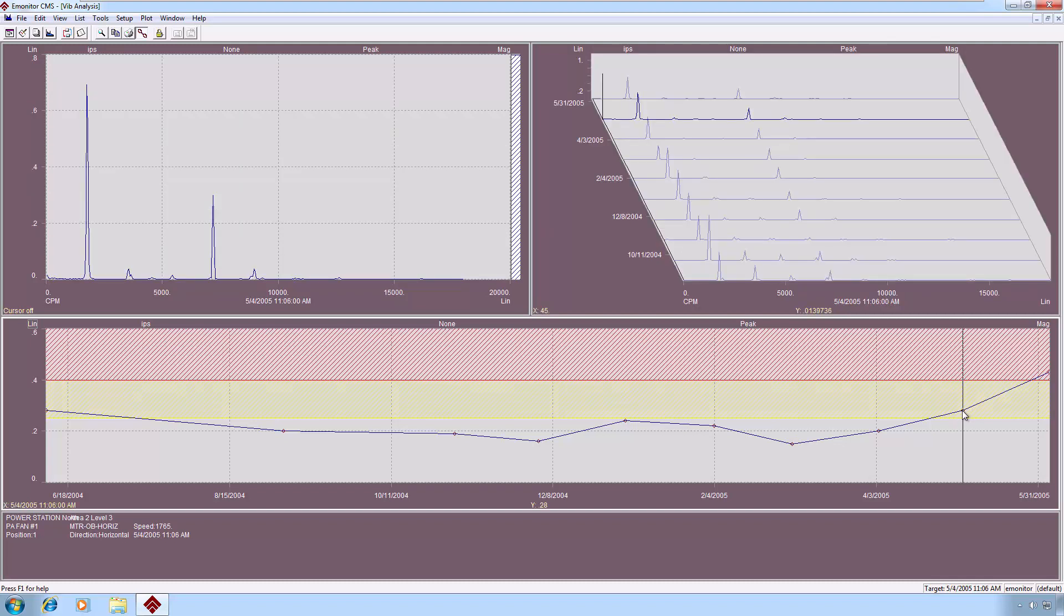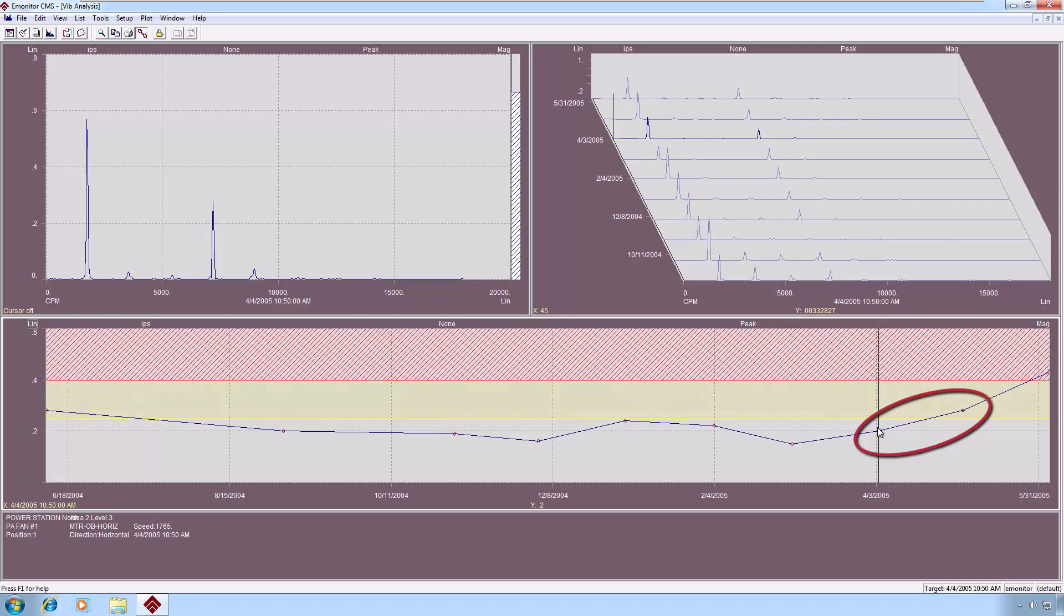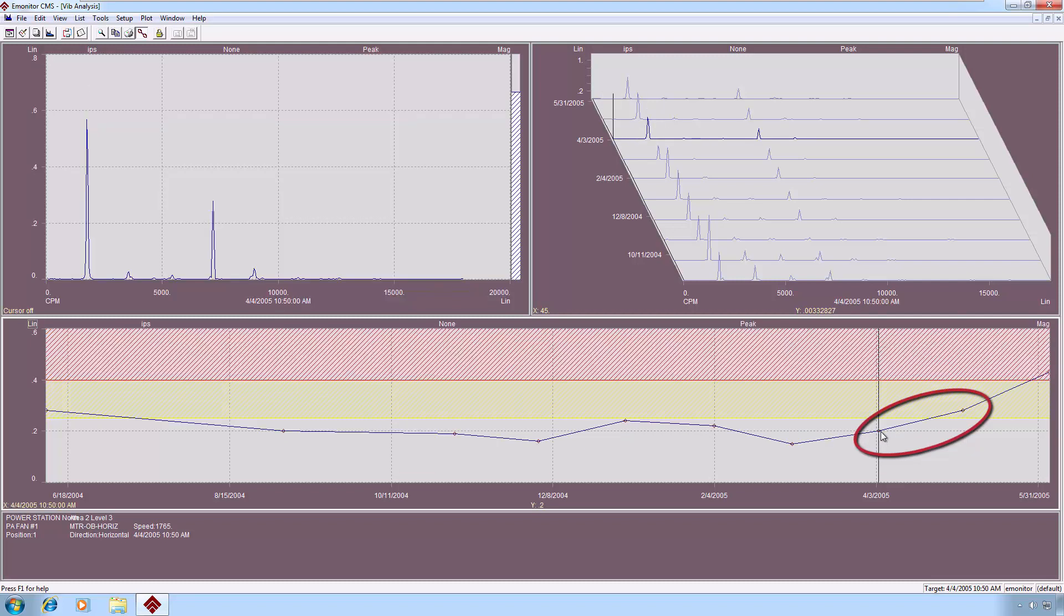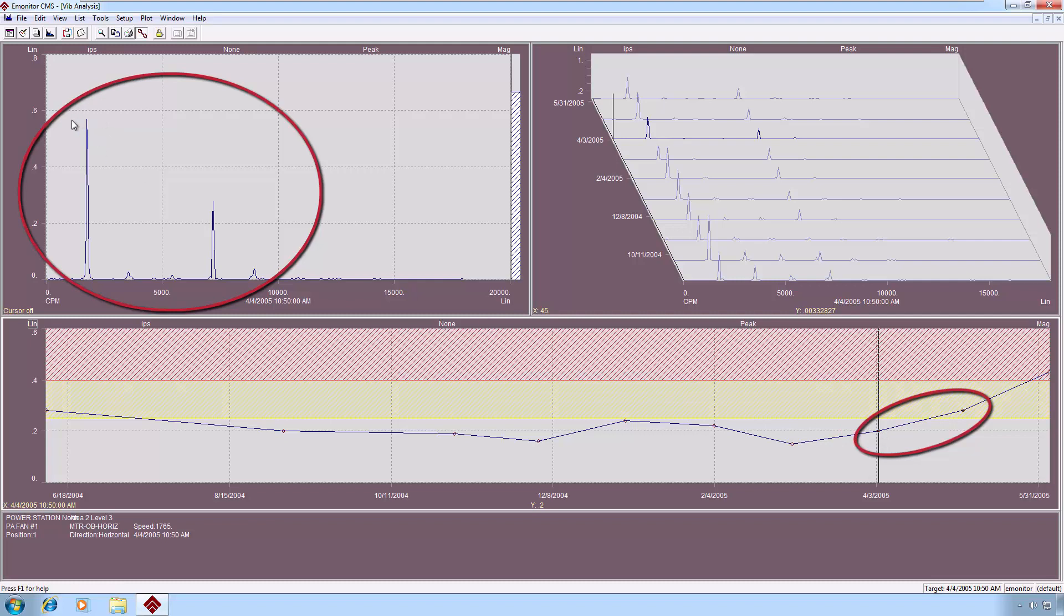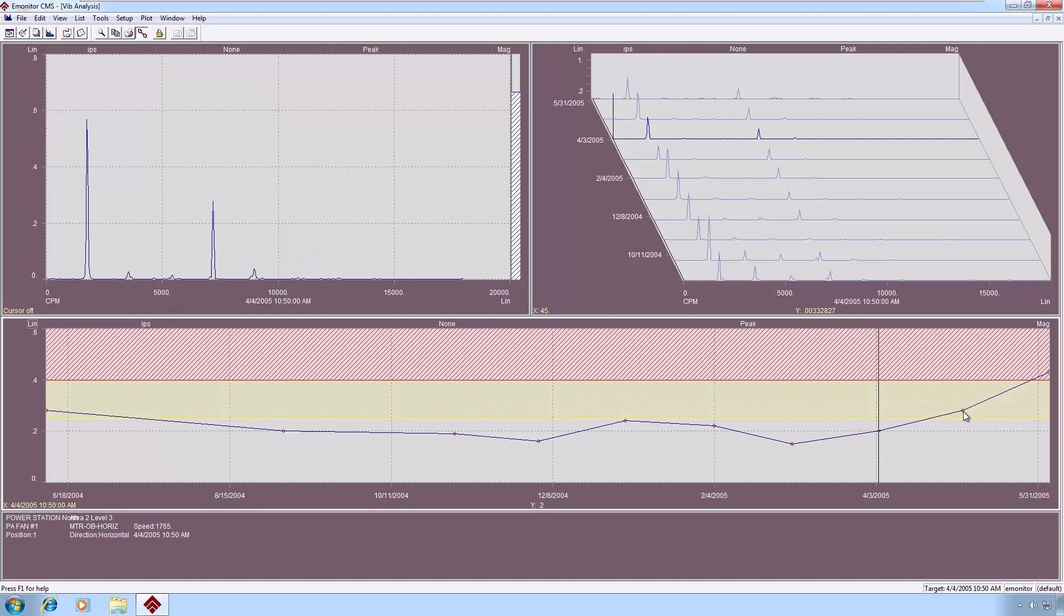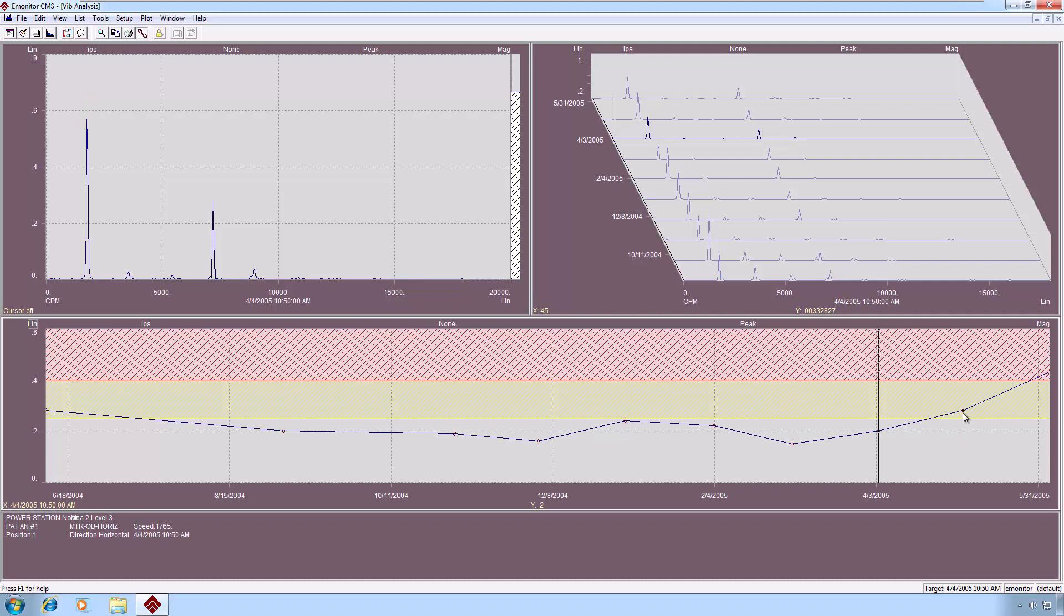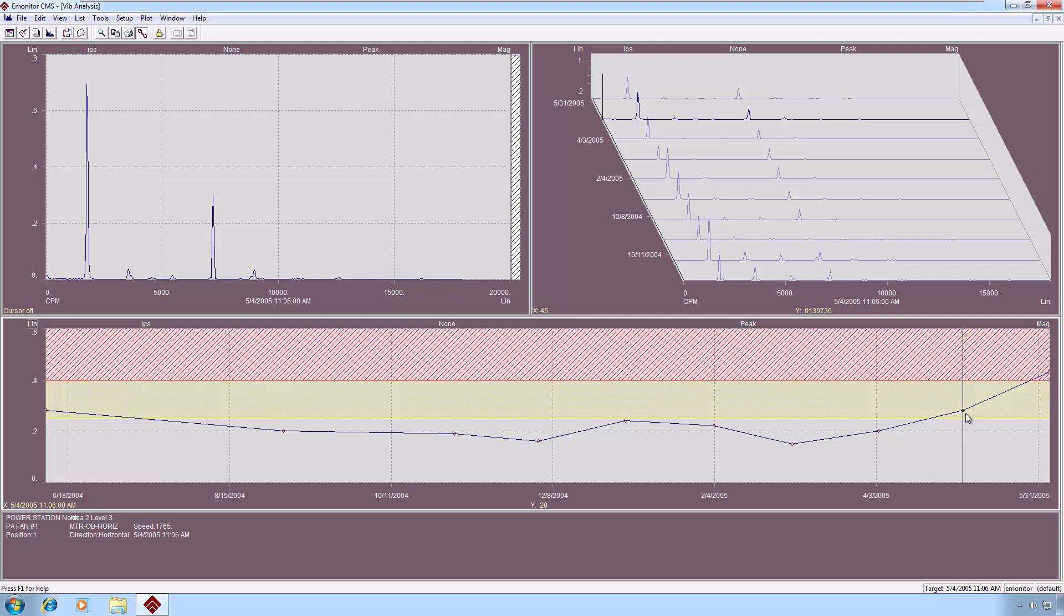So, if I want to see what has changed from this particular measurement to this one, I can take a look and see what's driving that energy. So as I click between these two points, you can watch and see that the overall has gone up, and the two times has gone up, just slightly. So that's just enough amplitude in those two peaks to drive a change in the overall to putting me in the warning alarm state. So that's a pretty handy view as well.